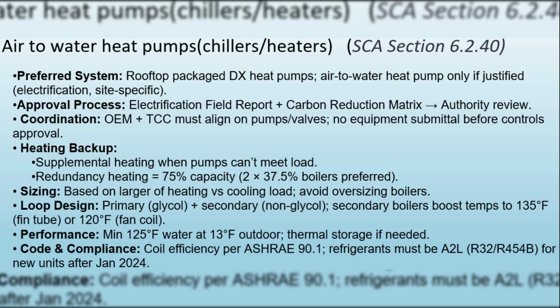Starting January 2024, only A2L refrigerants like R32 or R454B are permitted for new equipment in New York State, although older A1 refrigerant units may still be used if manufactured before the cutoff date. In short, while rooftop DX heat pumps are the standard, air-to-water chiller heaters can be a viable option if carefully justified, properly sized, and coordinated with controls and backup systems.